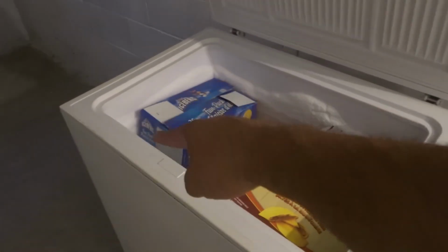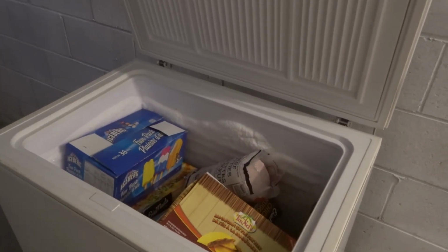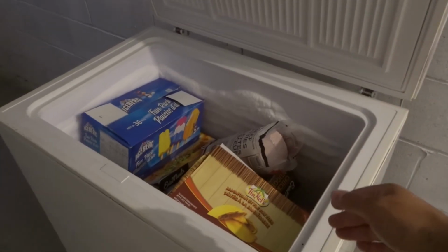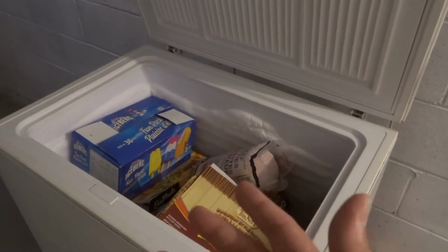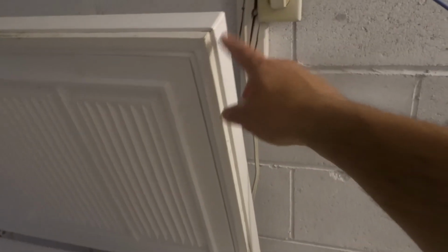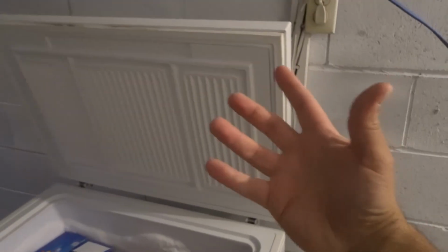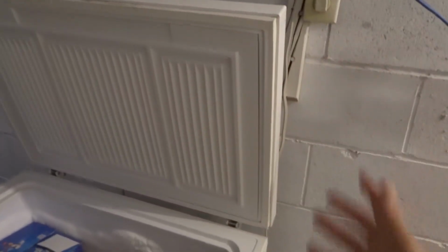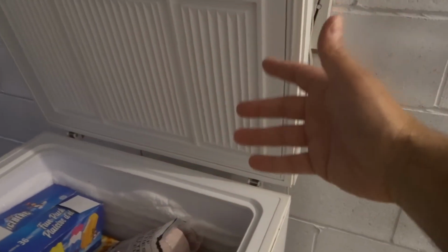Now you'll notice there is frost along there, and I did scrape off the frost about 8 or 9 months ago. I scraped off all the frost in here, so this is about 9 months of accumulation. And like I said, it's probably because of a multitude of reasons. Number one, the seal is old and pretty bad, right? And then it's humid in here because it's a cold room and it's the summertime, right? So that hot, humid air is getting in there. You get the idea. There's a few different reasons.